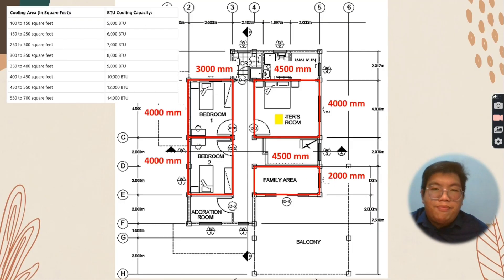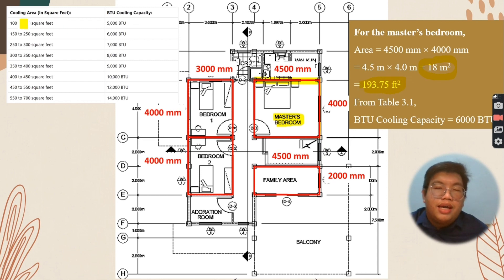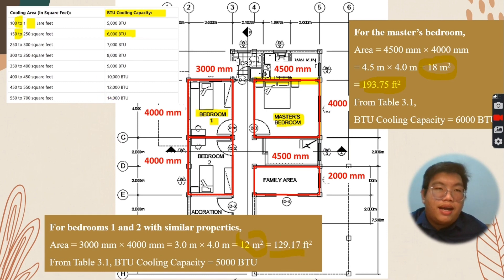For the master bedroom, the area is 4.5 meters by 4 meters, which is 18 square meters, converted to 193.75 square feet. Referring to table 3.1, that falls in the range of 150 to 250 square feet, so the BTU is 6,000. For bedroom 1 and bedroom 2, the area is 3 meters by 4 meters, which is 12 square meters or 129.17 square feet, falling in the range of 100 to 150 square feet, so the BTU is 5,000.